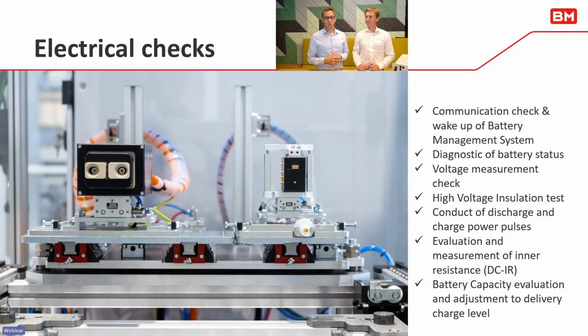Besides that, we would do the initial diagnostic of the battery and evaluate any kind of failures, or reset failures for the first ignition, which can occur during different assembly steps. After communication and the diagnosis of the BMS have been established, we can start the test procedure, which usually starts with a voltage measurement of the battery system, verifying in parallel the thresholds stored in the recipe, and counter-checking that the BMS measures the same value within the defined range.